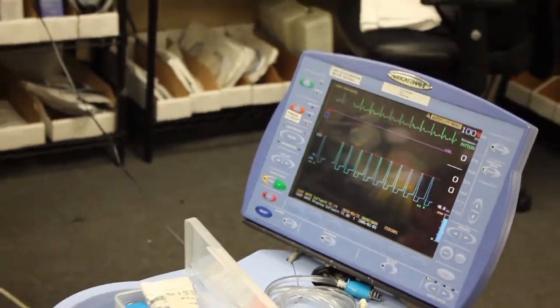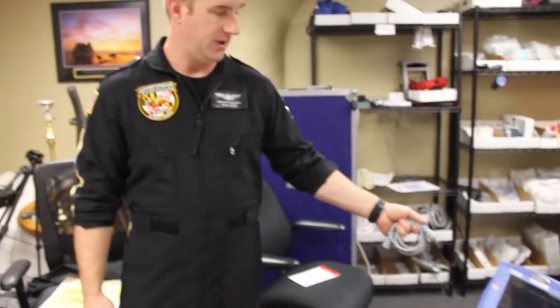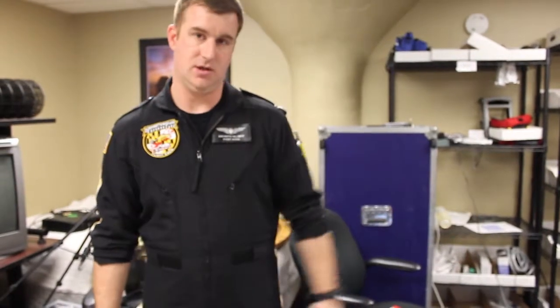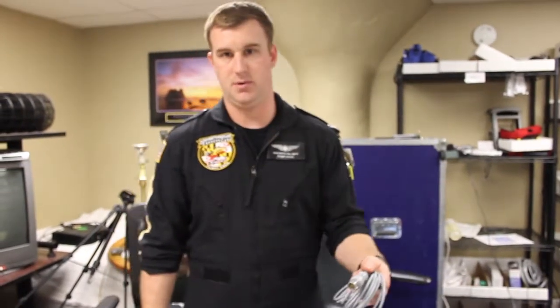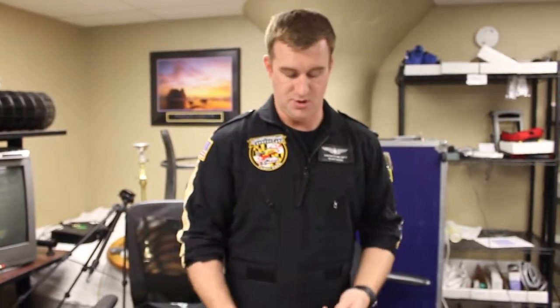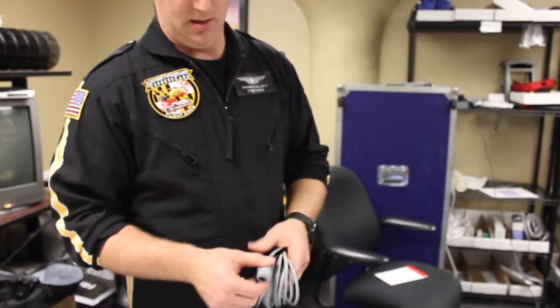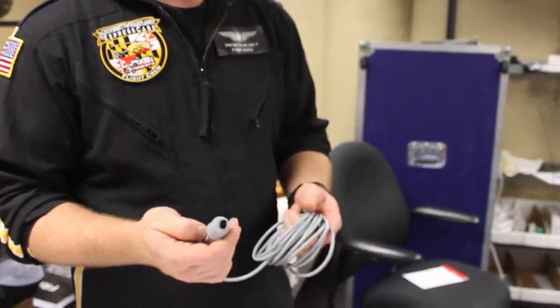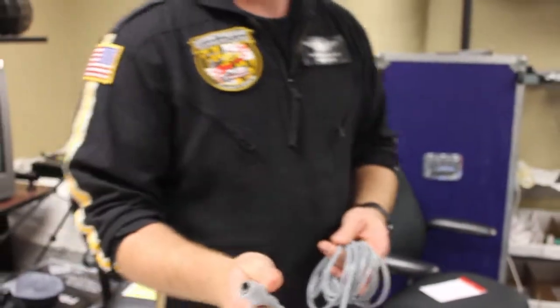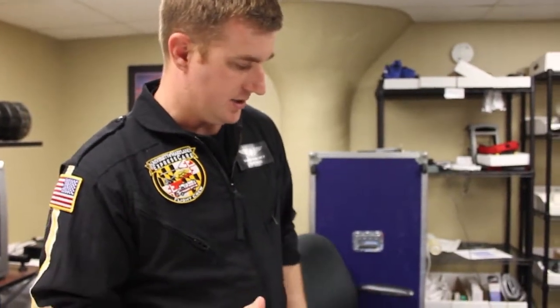Okay, so now we're on our balloon pump. We're pumping on our balloon pump, but we still have our AP source on the other one. So we've got the balloon pump switched over now. We're triggering on our balloon pump on an EKG source, and now we need to change over the AP source. We need to get the A line switched over. I'm assuming that the A line is already in whatever format your cable is. For us, it's the oval. So you go ahead and connect it up, disconnect theirs and connect your line. Go ahead and get it connected to your balloon pump.